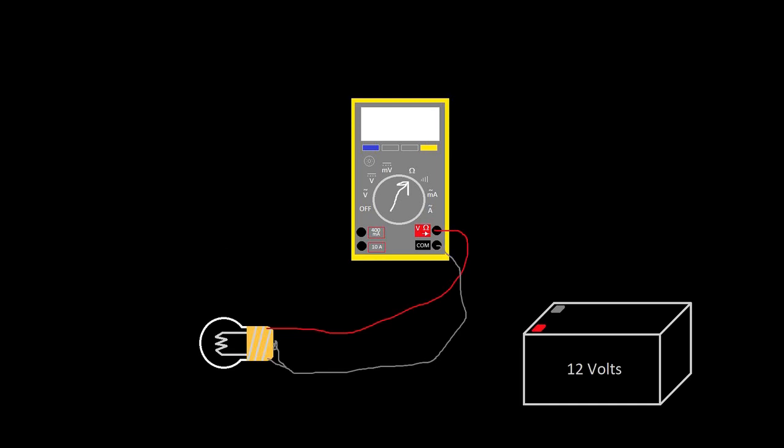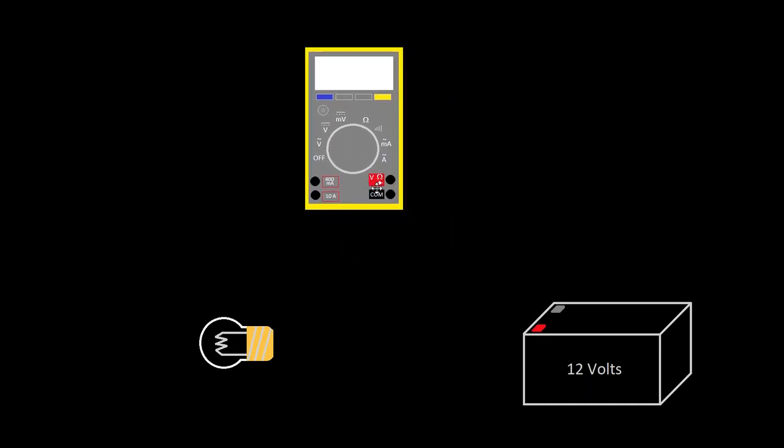Now, let's say instead of metering the resistance, we want to meter current. And this is where you have to be a little bit more careful. When you meter current, you have to insert your meter into the circuit. You have to make it part of the circuit. Whereas in every other case, we're just kind of T-tapping the circuit. You'd take your black and red lead and just go to the terminals of the battery or the terminals of a fire panel. However, in this case, you actually have to insert your meter as part of the circuit.